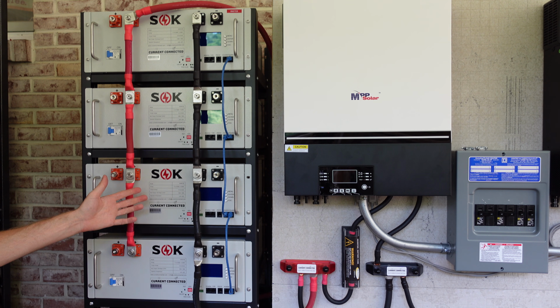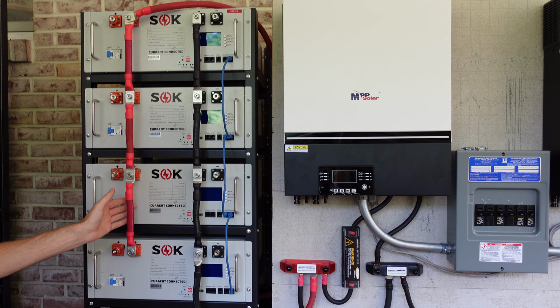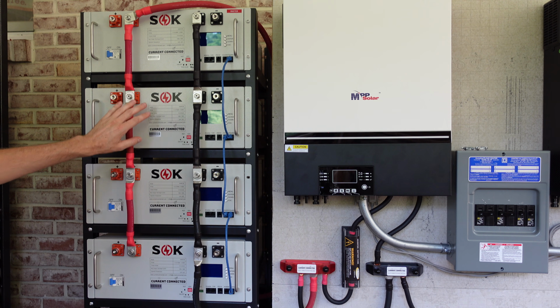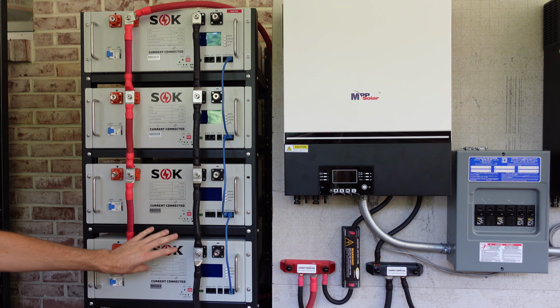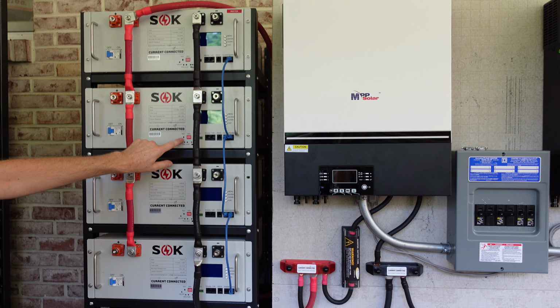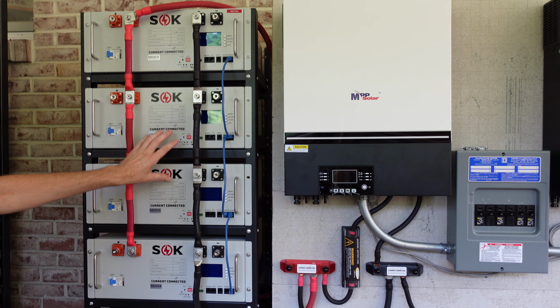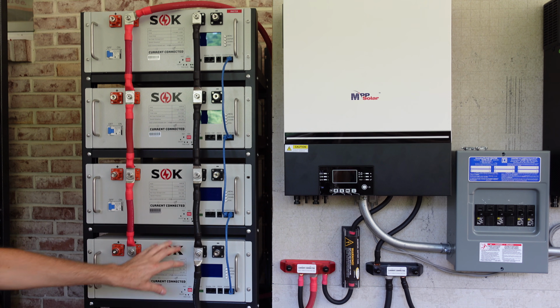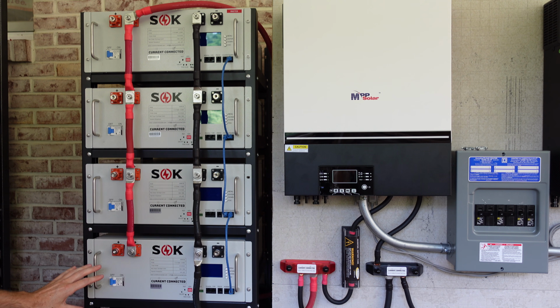Current Connected has a very specific way they want you to start these batteries up to help avoid damaging the BMS and the components of the battery during the first inrush of power when you first connect your inverter. I've turned off all of the BMSs on all the batteries. To do that, I just pressed in on the reset button for a second or two and it shut all the BMSs down. Additionally, I have all 4 circuit breakers turned off.